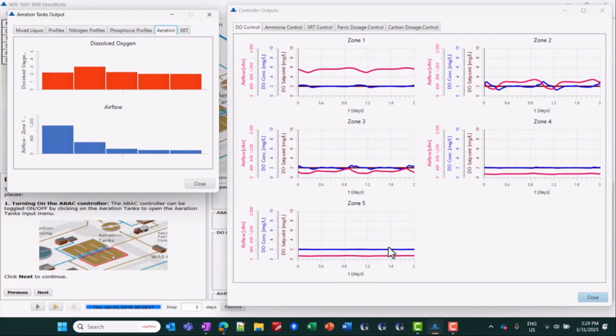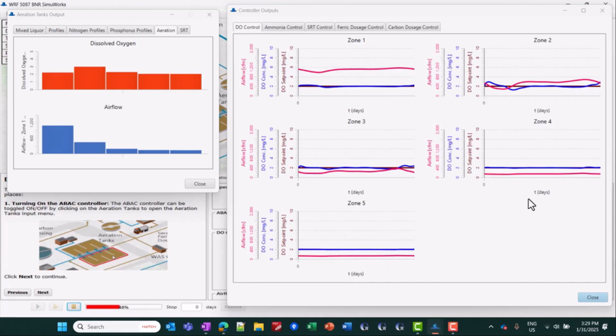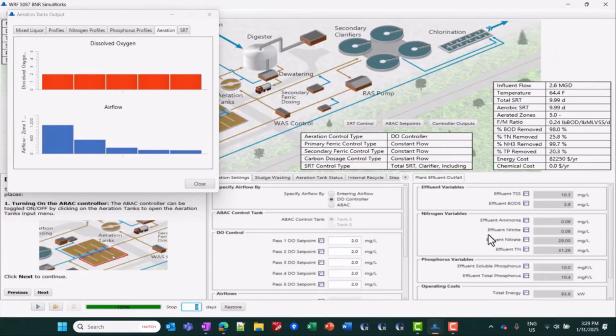Okay, so one thing that we want to see then is, and I'm going to rerun that steady state simulation, in this case we want to take a look at the amount of energy that's required to do DO control. So here we can see in this panel, the energy and chemical cost is being shown. And in this case, it's showing $82,250 per year to be able to run this DO control at 2 milligrams per liter. So that's because we're aerating up to a full 2 milligrams.